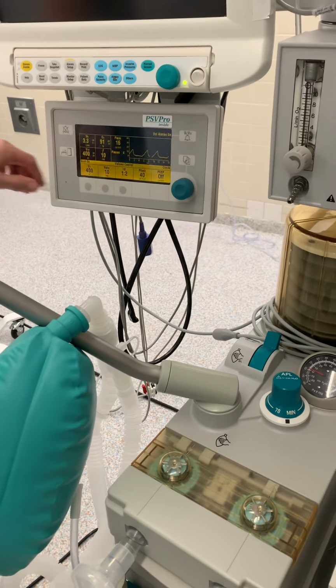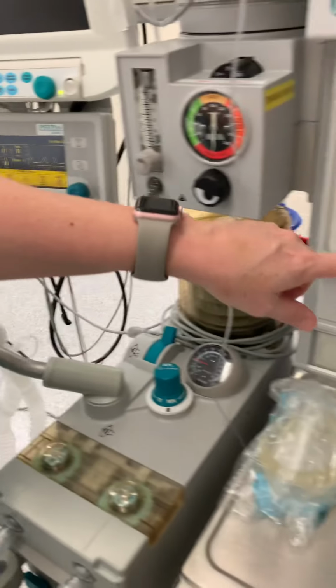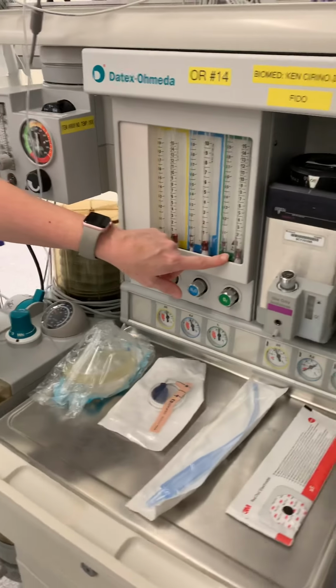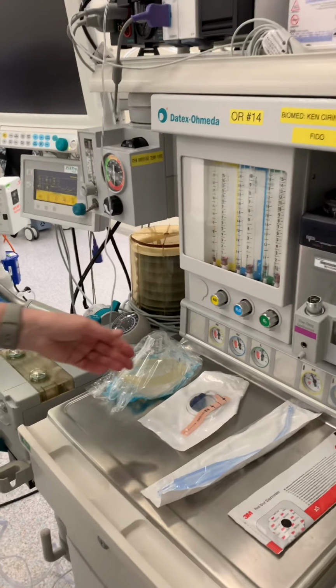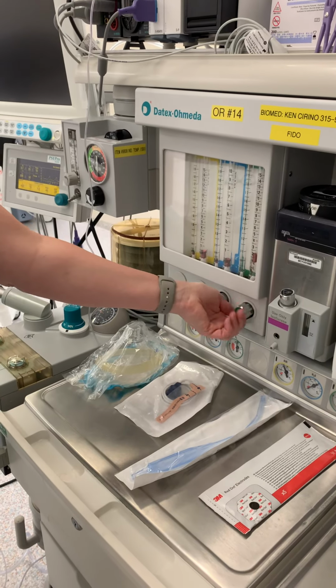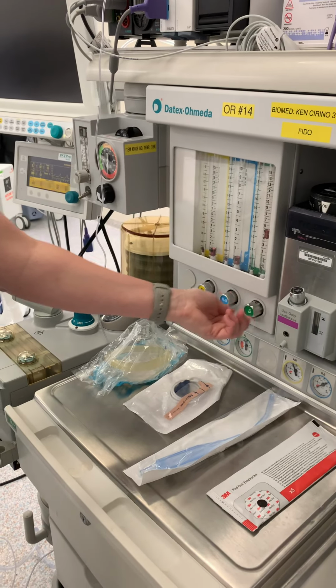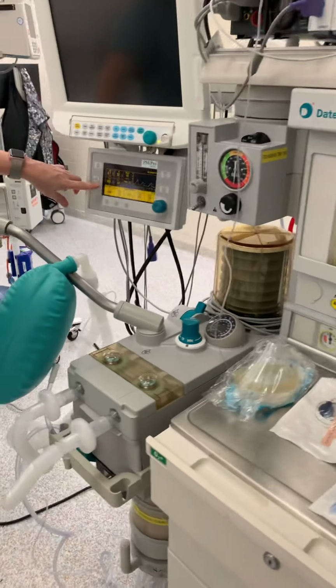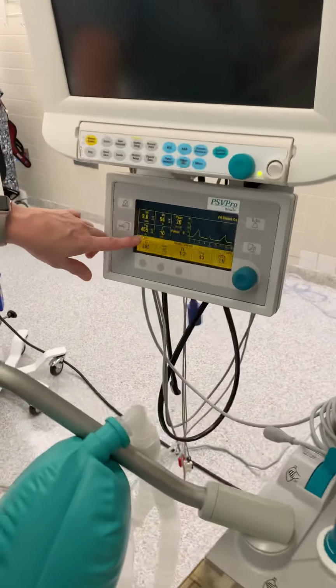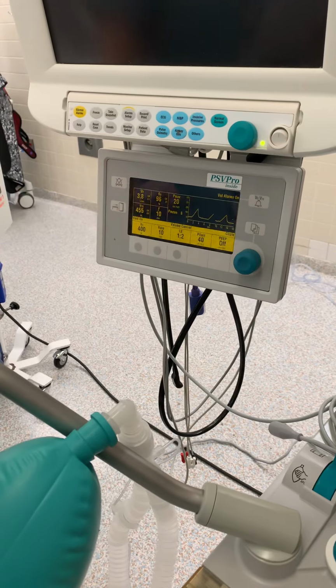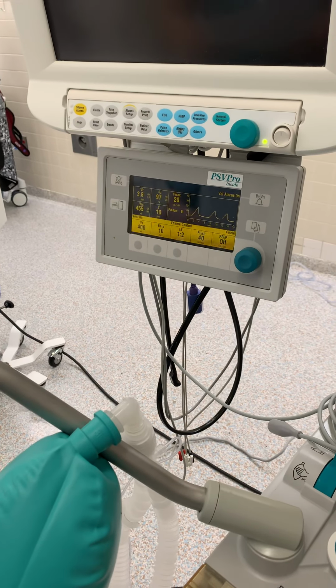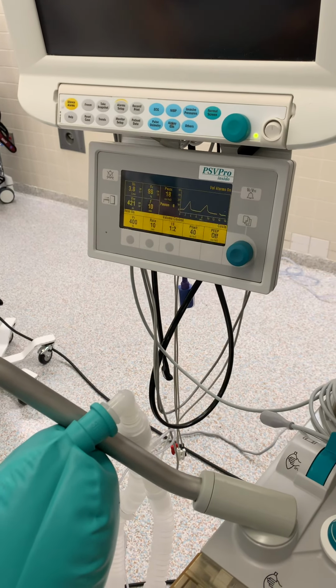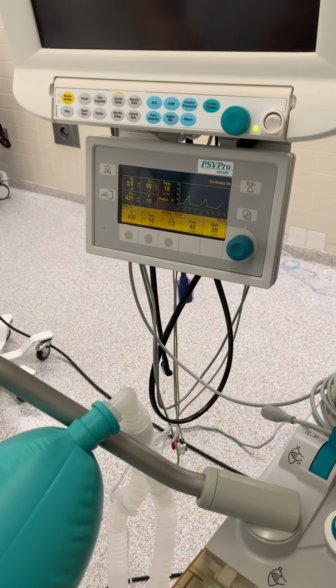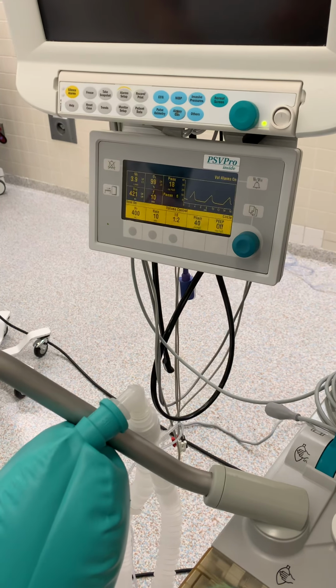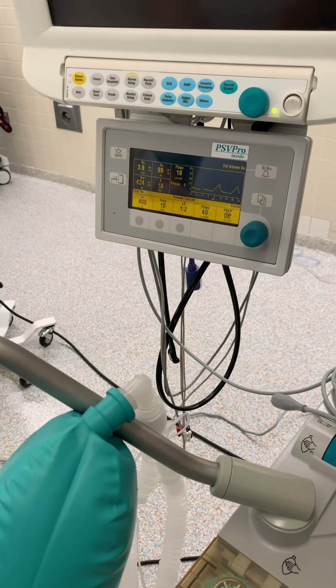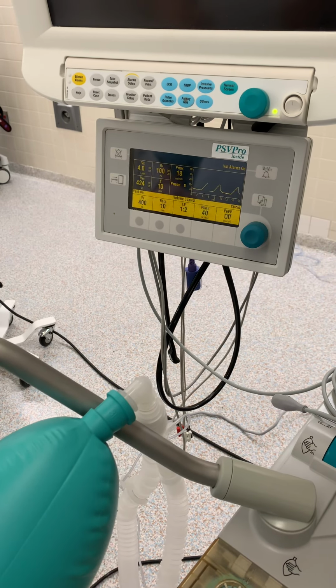With what you're getting back with your flow meter at 0, the next step is to increase your flow meter to 5 liters output, and you want to make sure that you do not have a significant change in your tidal volume. And if it does go up a little bit, that at least it comes back down to baseline.